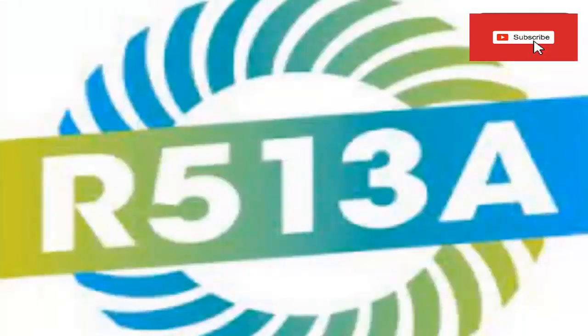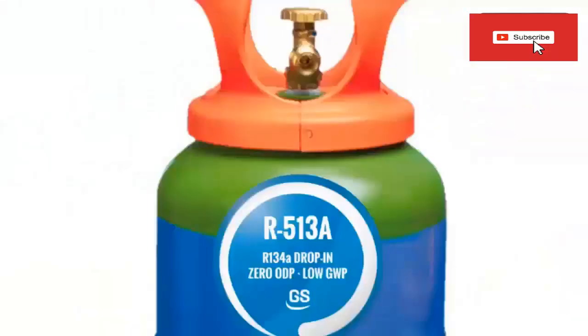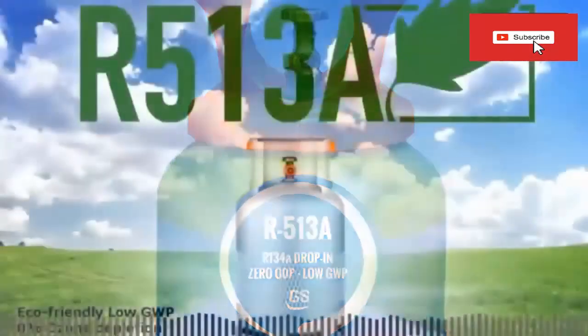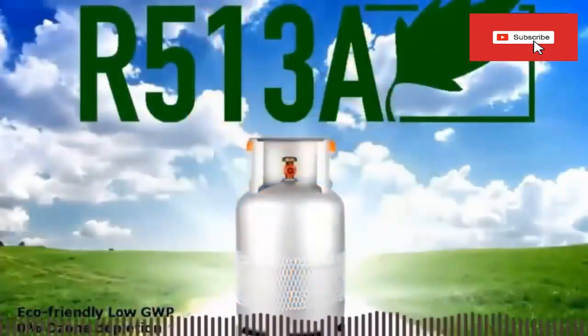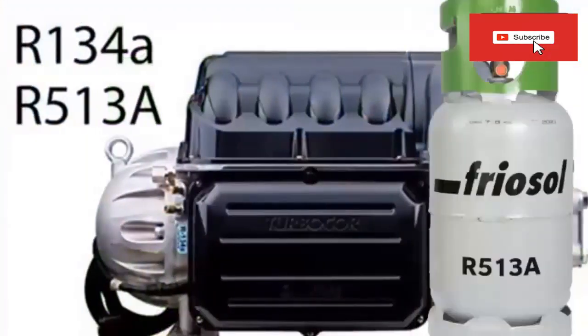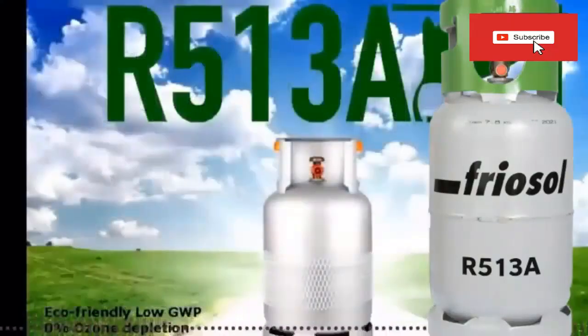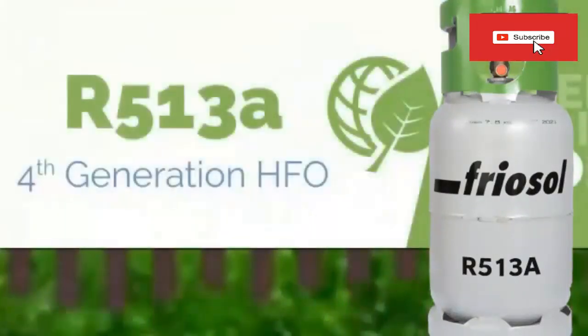5. In addition, R-513a refrigerant is presented as an excellent alternative in systems with centrifugal and screw compressors. 6. All Danfoss TurboCor series compressors, produced from December 2017, are compatible with R-134a and R-513a. 7. R-513a refrigerant is an azeotropic, non-slip blend.